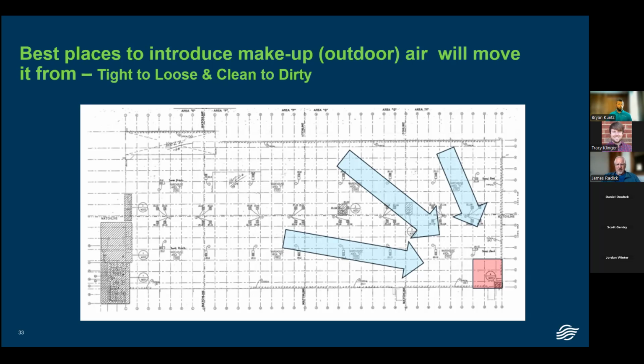But with a typical building that they're trying to conserve as much energy, but they're still looking for air quality and comfort, that hundredths of an inch water column will get them there with the air change rate. Again, it's exhaust plus estimated infiltration rate, the total of those two, add 10% to that, and that's the amount that you want to have for your overall system that's going into the building. And when you pressurize that building, now we want to introduce the air going from tight to loose and clean to dirty. The whole way to capture that nasties around that corner was to provide positive pressurization, which slowly moves the air, completely eradicating that nasty dust that was traveling all over the place.